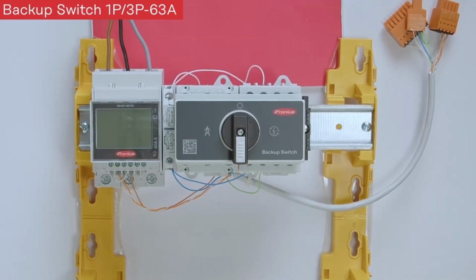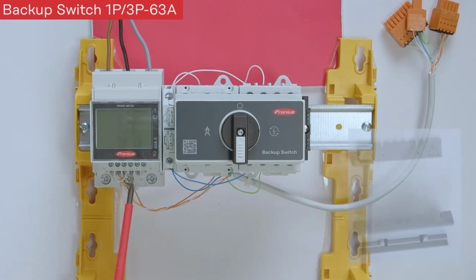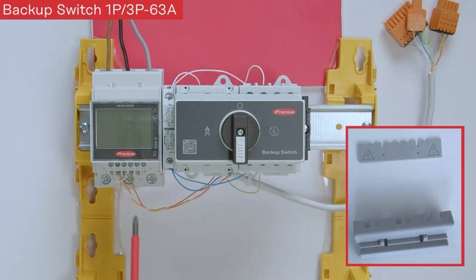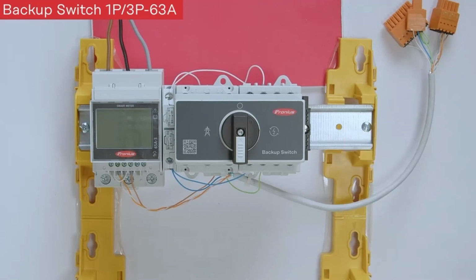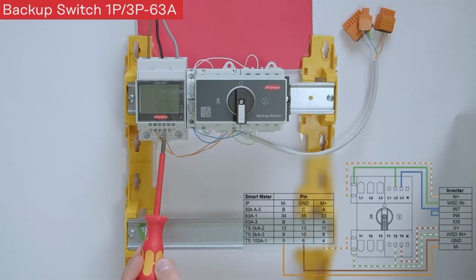Please note also in the user manual of the Fronius smart meter, you have two very important things. First of all, to note that you have here a protective cover to make sure that the data communication is separated from the phases on the smart meter. For the installation process itself, of course, we need to have a data communication, and this data communication first starts up with our Modbus RTU line coming here from the Fronius smart meter with 3 pins.